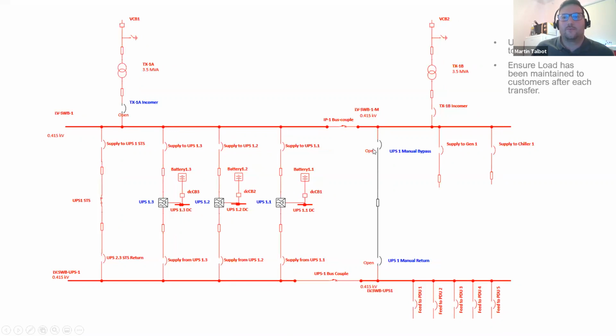When we're doing this switching, we don't want personnel in front of the switchboards operating the gear as far as possible, unless they have to be. So where possible, specify remote switching and get your employees to carry out that remote switching. It might be in the same room, but as long as they're not stood in front of the panel or switchboard, that's always preferable.